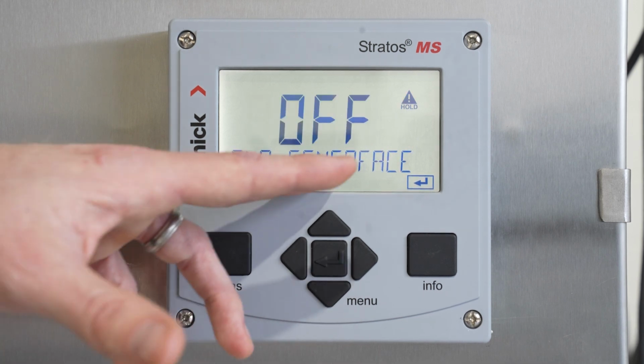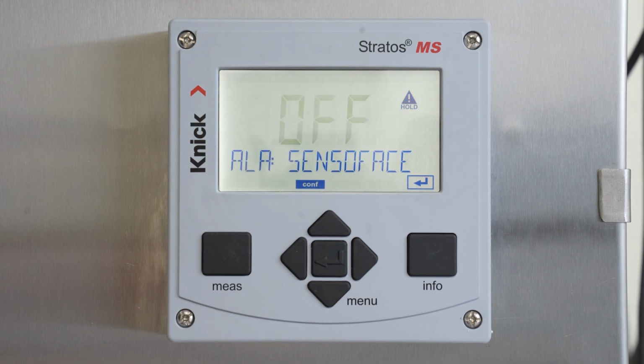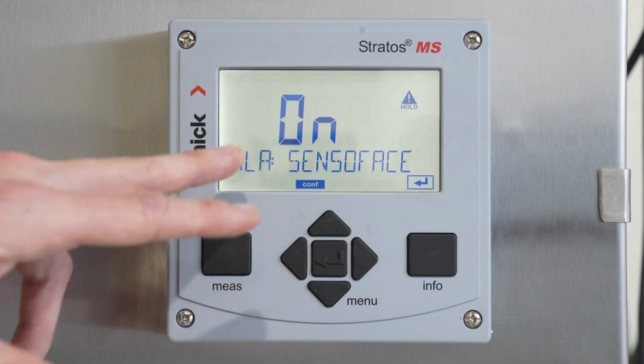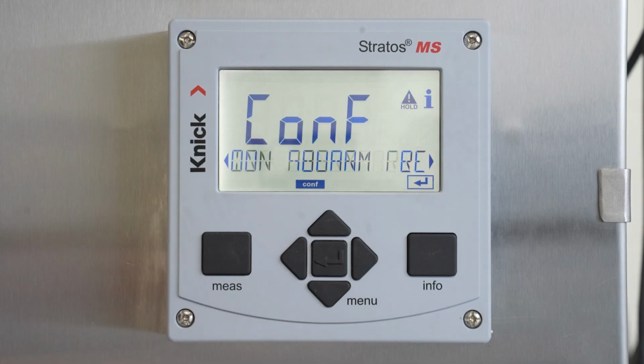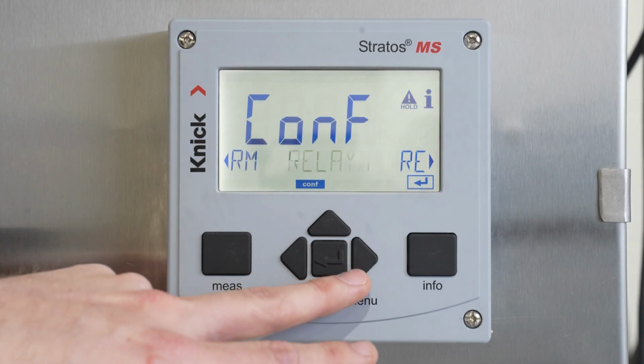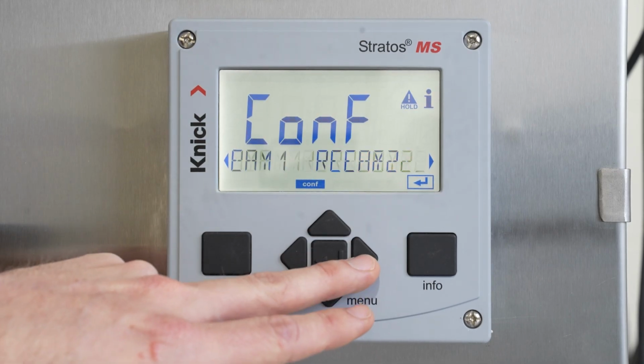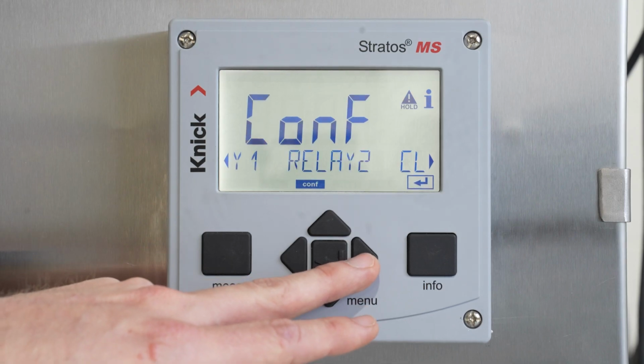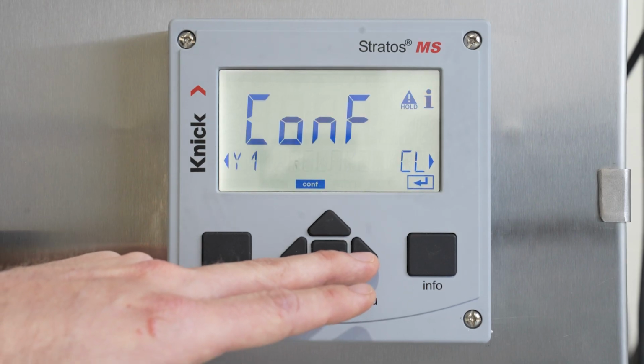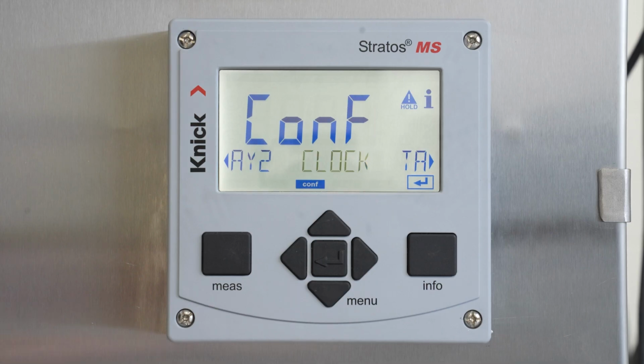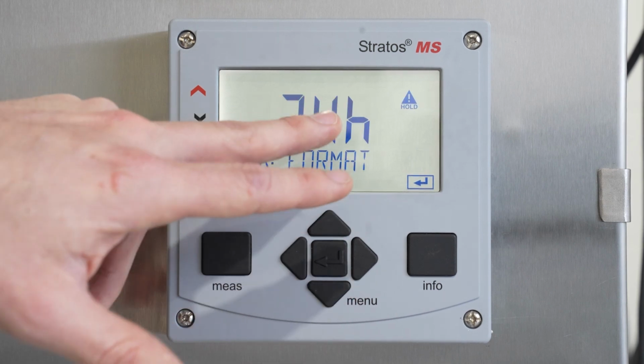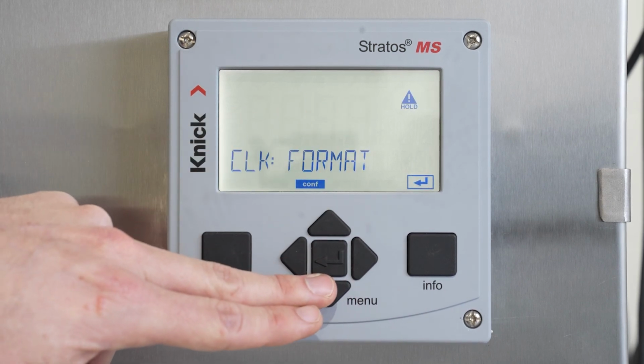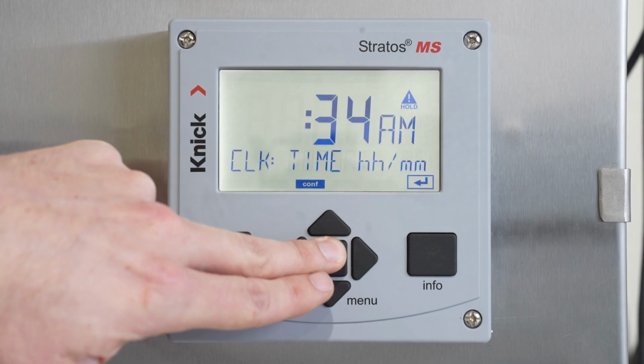Pressing enter, you will see the option to turn on or off our Sensoface on the main measurement screen. We recommend leaving this feature on. Lastly, you will see our Relay 1 and Relay 2 contacts, which are freely configurable by you, the end user. Finally, it is very important to set up our clock for our date and time on our Stratos MS transmitter. Here you can see we have the option for 12 or 24-hour format.